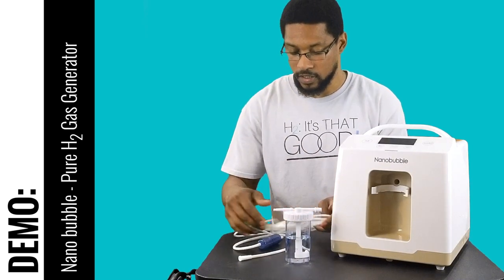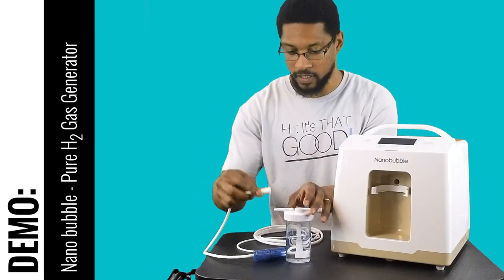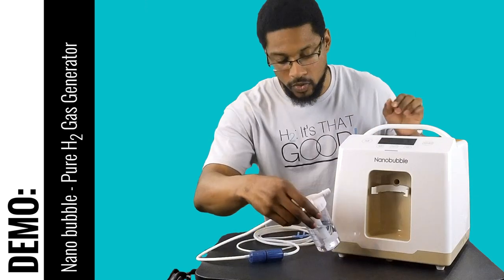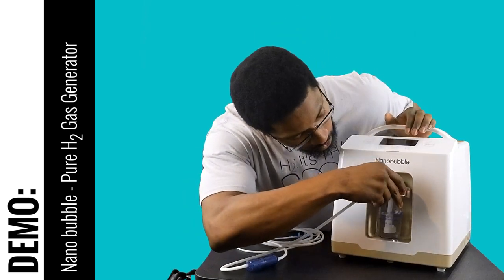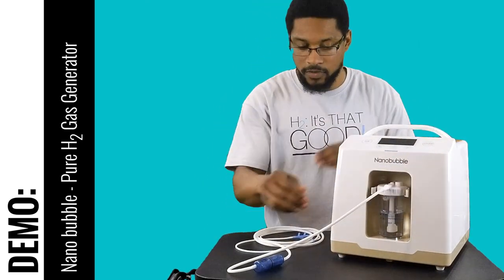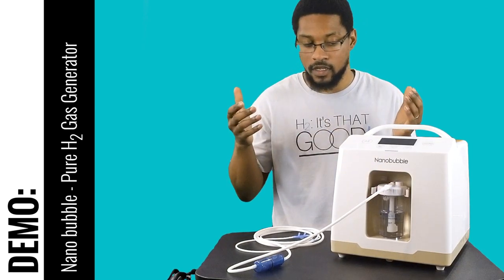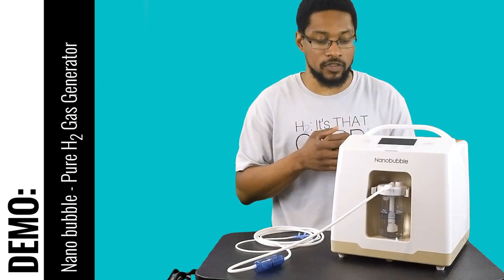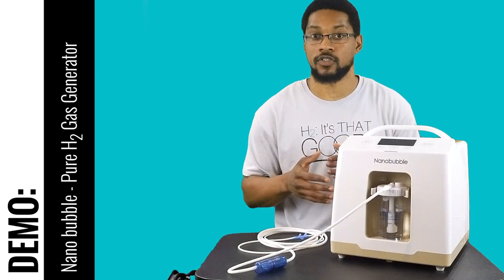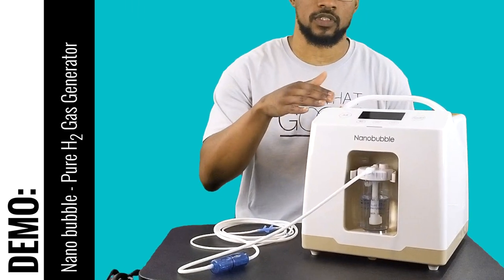When you have it off, you take this part of your cannula and press it onto the tip of the humidifier, then slot it into the holster and push it into place. You don't have to push too hard, just enough to create a good seal. Your nasal cannula is then fully set up to use. You power the system on after adding the water. Now that the master switch is on at the back, we can actually power the system on.